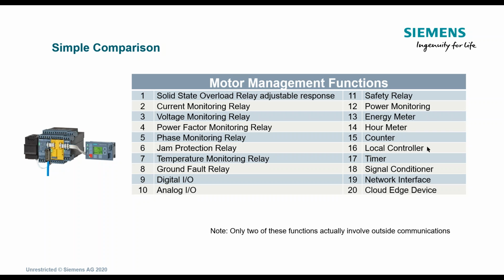Again, I said it is a local system. You can have it not tied to a PLC or a controller. It can run all by itself in a pump panel or a standalone application. I have timers built into it. For instance, on that jam module, when it jammed once, I started a timer, and if it jammed again within 5 minutes and went in the same or reversed direction again within those 5 minutes, then the machine stopped and sent a signal to the operator to say there is something major going on. But if it didn't jam again after those 5 minutes, then it just reversed and moved on with the process. But there's the ability to use timers.